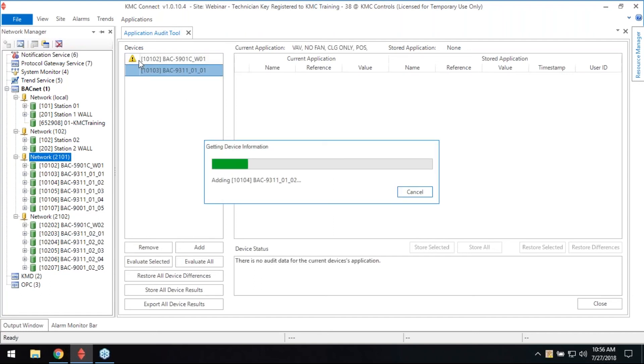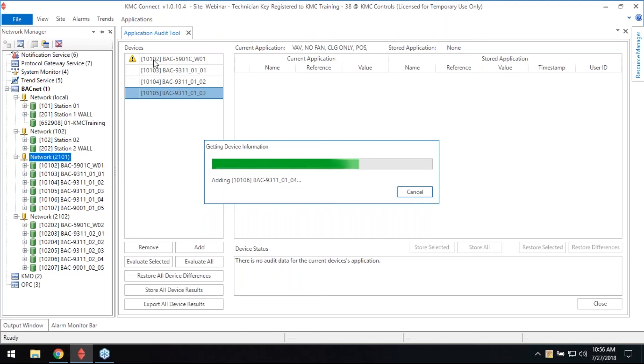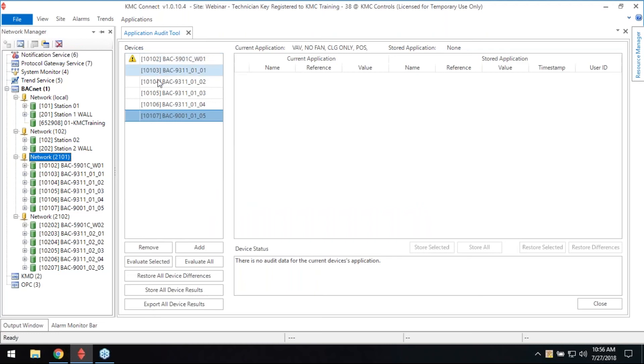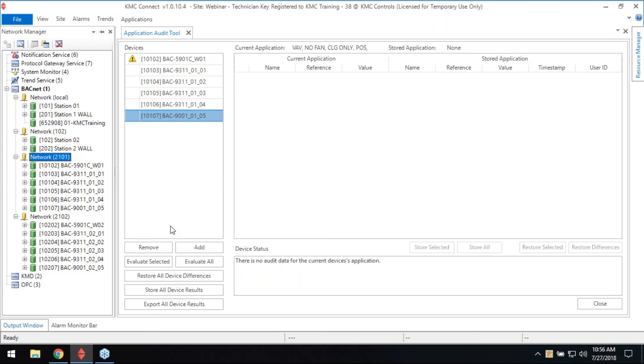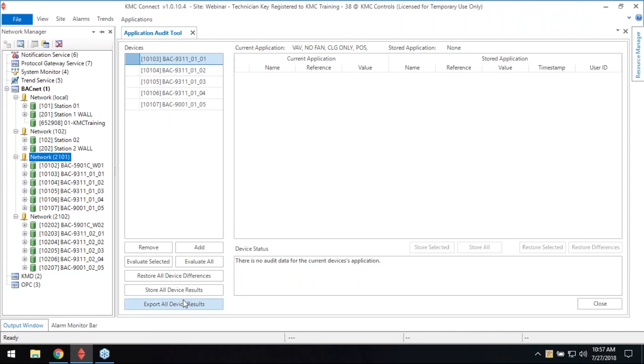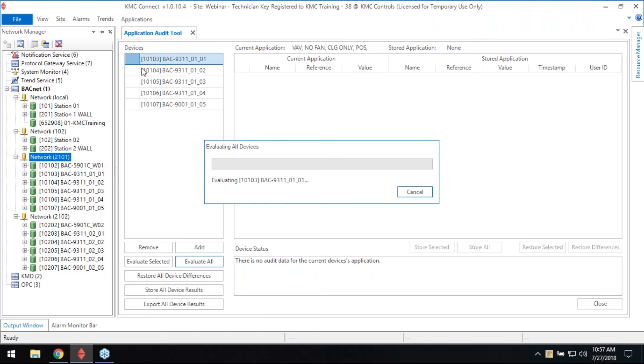It's pretty simple and fast to do. We're going to bump into a little problem probably because I didn't actually run the deployment. So that guy right there, it's a 5901. The audit tool doesn't know what that is. If I had actually pushed down the custom app, then it would know what it was. We could do this per network, we could do the whole building. It's fairly fast to do the audit. I'm just going to show you on this side. I'm going to get rid of that guy. These are the VAV controllers. If you have something on this side, this is in our database. I'm going to evaluate all right here. That means everything over here I'm going to evaluate.